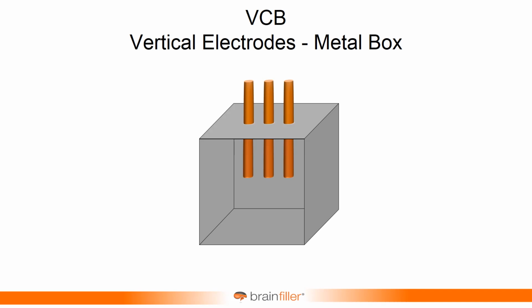So my own diagram of this, you have the 3 electrodes in the box, and I put the trigger wire across there. That's not the trigger wire there. That just indicates where the arc is being established. The trigger wire is actually higher up on the electrodes. And so you get the arc established. This is almost instantaneous. And then the energy shoots down, but it then works its way out. So it comes down and then out, spills out.